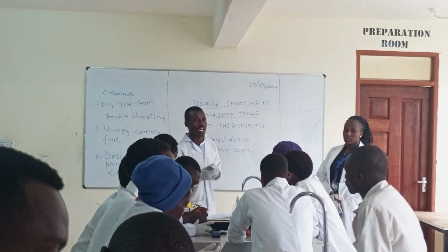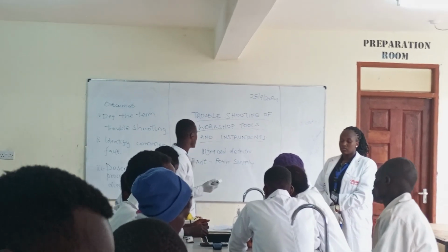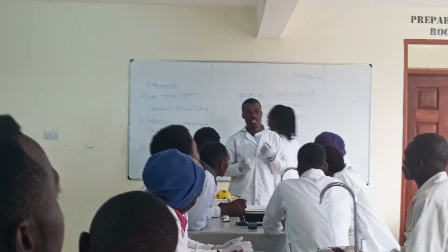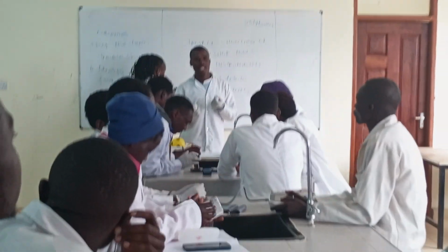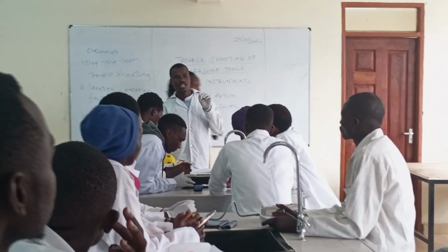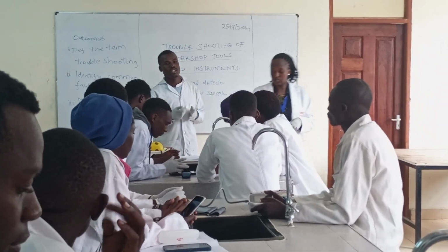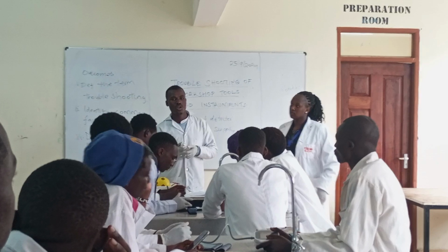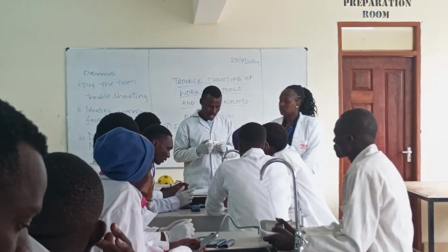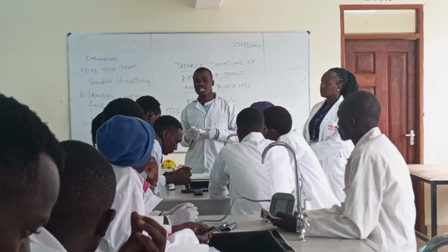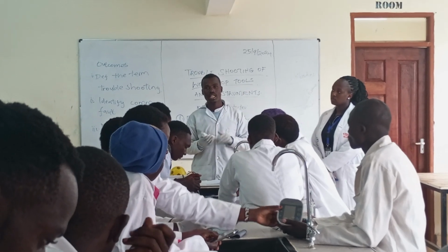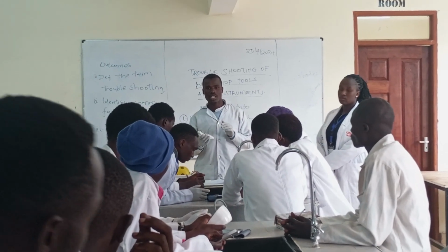So we said the gun thermometers use the infrared detector to measure the body temperature. Okay? They can detect temperature without contact. And so with our gun thermometer here, we realized it had a fault with the calibration.